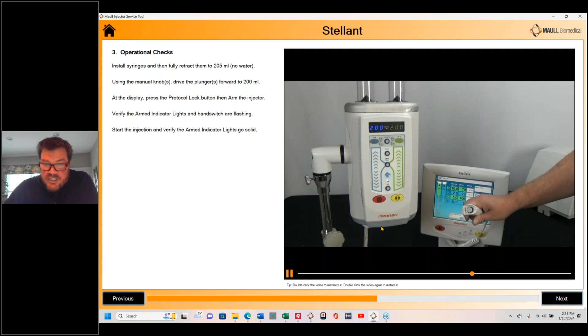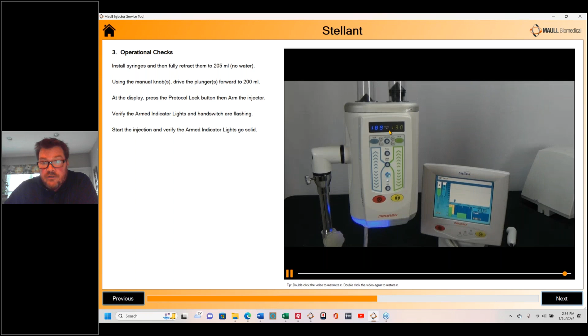as you can see here on my display, these are the protocols that we were putting in. 325 psi is the pressure limit. So we're showing how to fill the syringe, and we're moving the pistons forward to 200 milliliters, and we're going to start this injection at the 200 milliliter level. And we're basically just showing the operator how to arm the injector and make sure it's ready to shoot. And remember earlier I mentioned these green and blue LED lights. Those are the green and blue LED lights right here. That's the start switch. And then as you can see, my piston is moving. So we're basically just making sure the arm lights work, the injector lights work, and that the actual injector injects when we hit the inject switch.